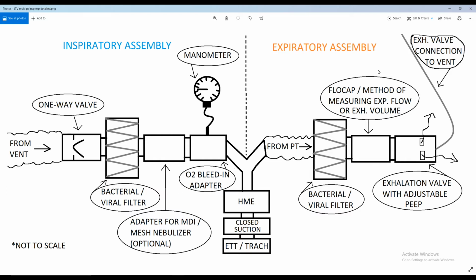Now switching over to the expiratory side, where would all this dirty, potentially viral droplet mucus-filled gas go? It would come out of the patient, go down a little run of corrugated tubing, as it usually does, and then that corrugated tubing would have another bacterial viral filter connected to it. This would be to keep the staff safe, obviously, and make sure that they aren't spraying stuff out of their vent circuit. It would also stop goobers and a decent amount of moisture and things from getting to this portion and this portion, which I'm going to detail here in a second.